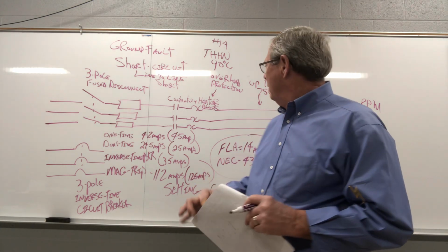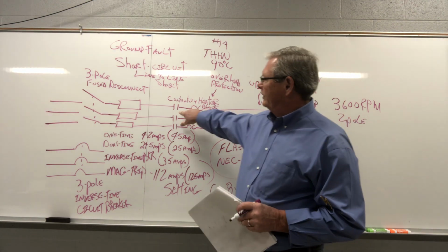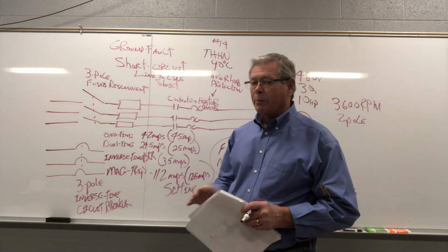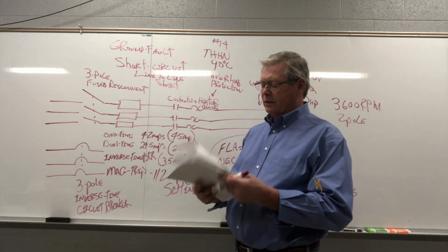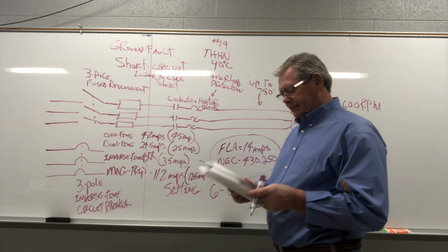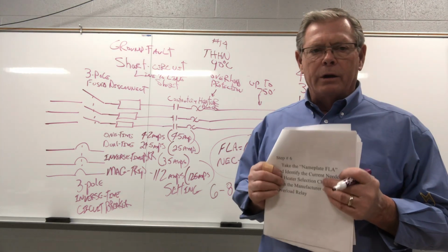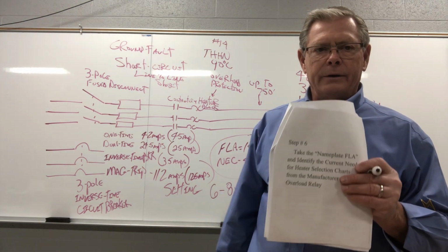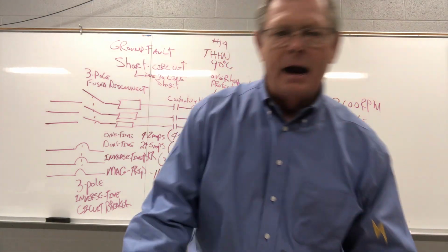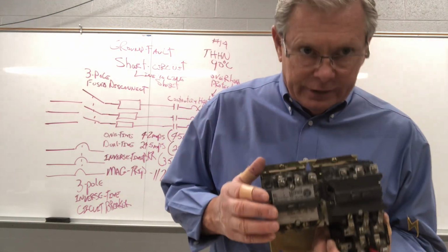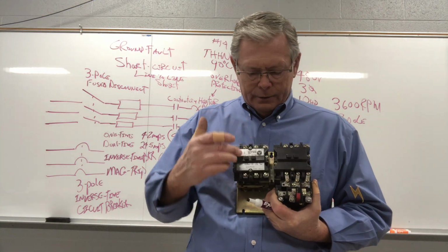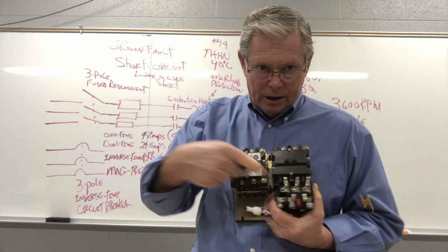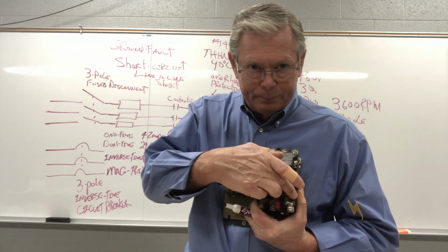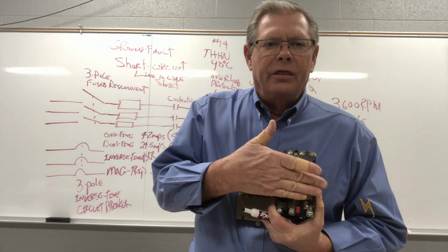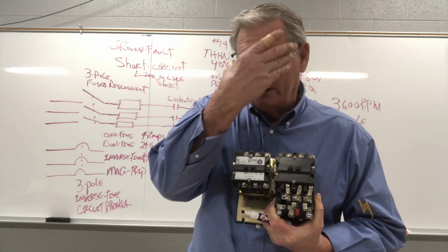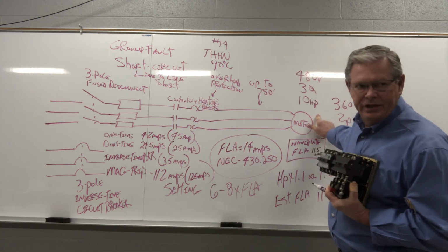Okay? So now, we've determined what size wire, what size starter, what size fuses and or breaker, and how to set our instantaneous overcurrent. Now, step 6. Now we are going to determine how to size our heaters. This here is a reversing starter. Contactor, heater block, where my hand's at. These 3 places here have heaters. This is where we custom fit the overload protection to this motor.